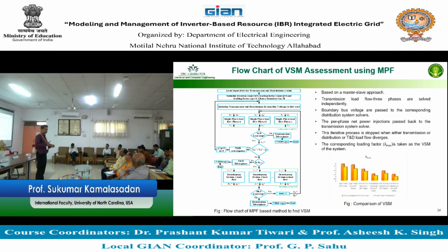So you do interconnection study. This has to be done, and normally it will be done. I think here also somebody is doing that, and the US people are doing that. But none of the interconnection studies do this kind of study, which I think is important. It's dangerous if you connect the PV farm without it, because location you cannot change. That is decided by policymakers, government, some other people. It's nothing to do with technical people. The only thing you can do is strengthen.